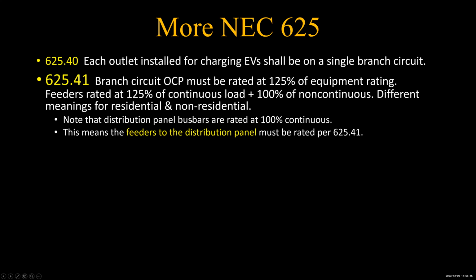Distribution panel bus bars are rated for 100% continuous operation. So if you had a 200 amp panel, that means you could operate it with 200 amps on the bus bars continuously, because that 200 amps is not going to go down the entire bus bar to the bottom. The first 2 breakers on top are going to pick off whatever they're going to take, and they're usually the bigger ones. So by the time you get partway down, the number of amps on that 200 amp bus bar is going to be down below 100. So not nearly as much heating. It's all right at the top where the utility comes in. Unless you got some solar coming in at the bottom, then it reduces the load at the top. That's another story.